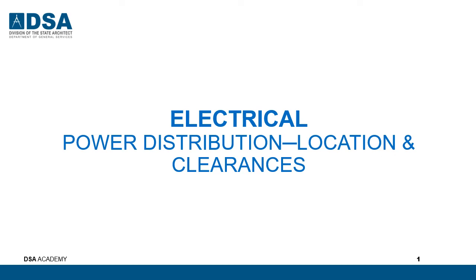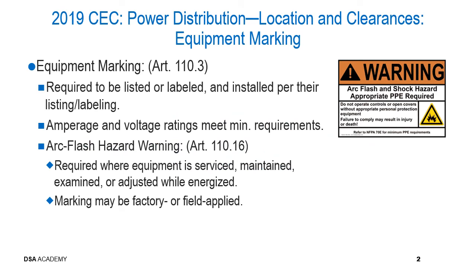We'll continue now by discussing power distribution, specifically location and clearances for power distribution. Let's start by talking about how power distribution equipment is required to be marked. Obviously, the equipment needs to be marked, and the requirements for marking of power distribution equipment is found in Article 110.3.